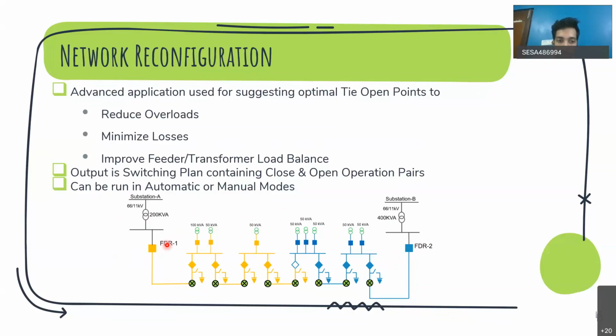So 50 kVA will go from here to here. Then it will be 150 out of 200 and this will be 300 out of 400. So in this way, the overload is reduced this side and they are also equally balanced. They are both at 75% load. Okay, so based on your requirement, network reconfiguration can be run. So this is one more advanced feature.